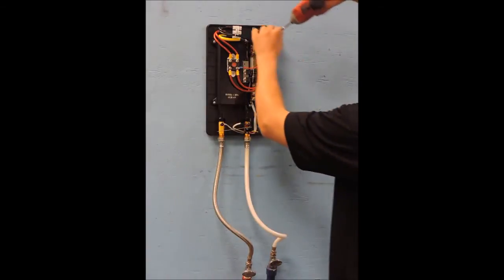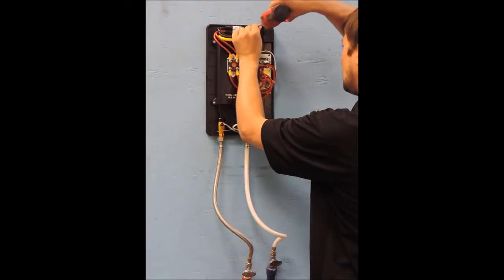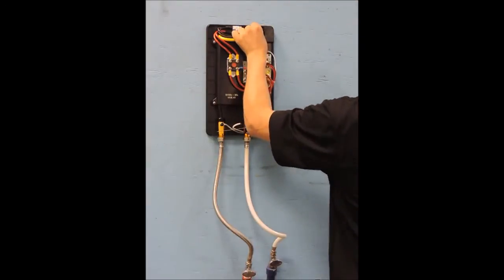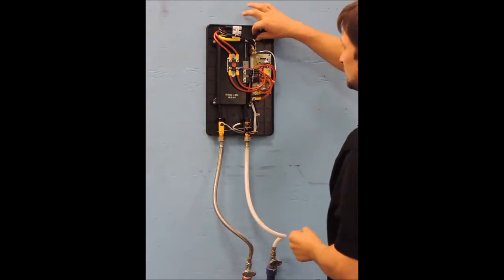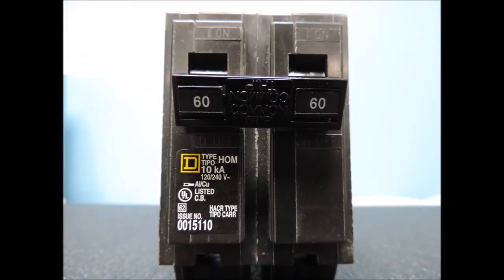Before moving on to the wiring, be sure to free the wire retainer to ease the installation. The power for this unit needs to be supplied by a 60 amp double pole breaker.